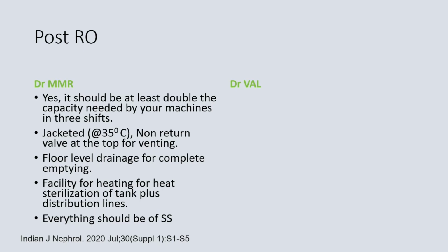One has to make sure that both the inlet and outlet valves are kept open, because once what happened was somebody closed the outlet valve, so the water pressure in the jacket rose so much that it actually crushed the stainless steel tank, and we had to redo the whole tank. And it has to be stainless steel, and should have a venting system with a non return valve at the top. Your last drop of water should be able to be drained from a floor level drainage, and there should be a system for either heat or chemical sterilization for injecting into it.